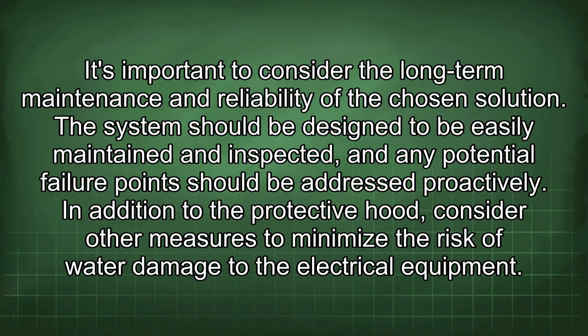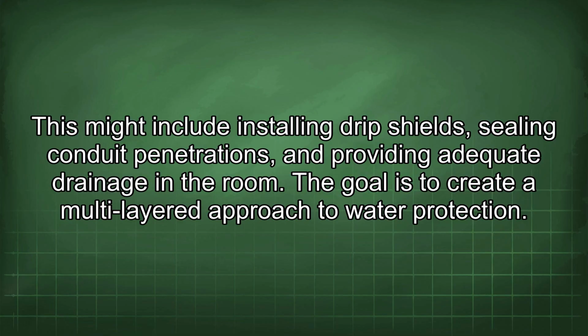It's important to consider the long-term maintenance and reliability of the chosen solution. The system should be designed to be easily maintained and inspected, and any potential failure point should be addressed proactively. In addition to the protective hood, consider other measures to minimize the risk of water damage to the electrical equipment. This might include installing drip shields, sealing conduit penetrations, and providing adequate drainage in the room. The goal is to create a multi-layered approach to water protection.